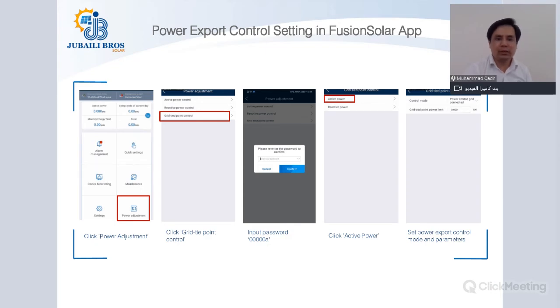Power export control setting in the FusionSolar app. Now you have detected your inverter, you have detected your smart power sensor, either by manually adding it or by automatically adding it. So the third option within the same commissioning phase, you will find on the left window, is the power adjustment. You will click that. That will prompt you to the next window where you will find the option of grid tie point control. So you will click that. Since you are doing some sensitive setting right now, the inverter will ask you to put the password in order to go ahead.